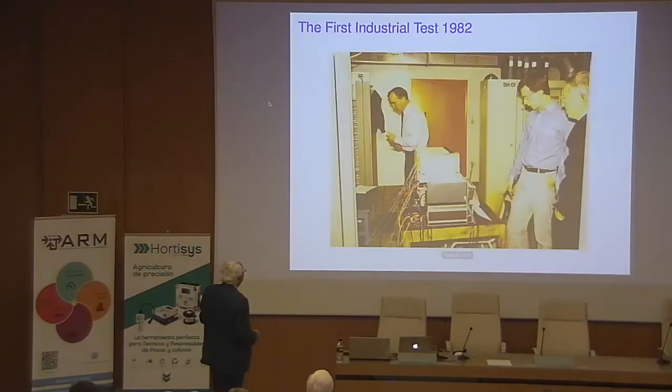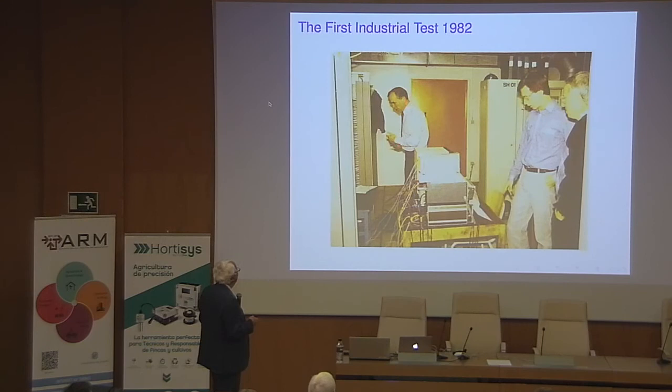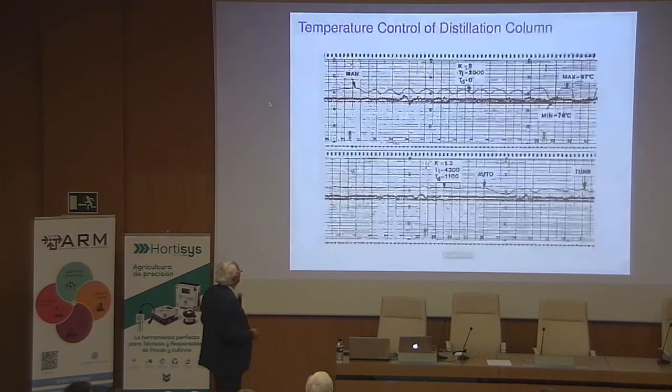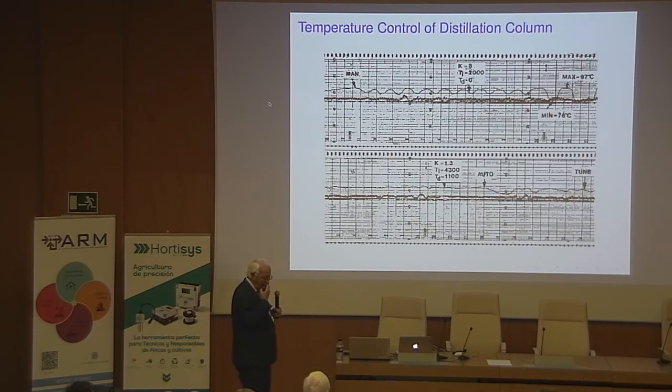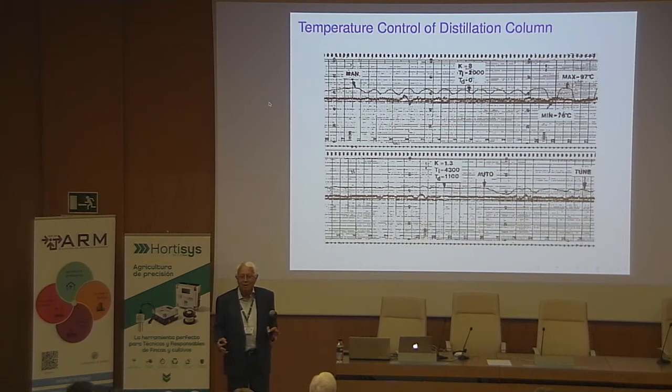Here is a young Tore, and this is the first industrial experiment we did at a sugar refinery near Lund. The computer was an Apple II with the code of the first relay auto-tuner — I actually wrote the code. When they were trying out the STM-20 system up in the north of Sweden, normally commissioning takes a couple of weeks. With the auto-tuner, they did it in two days: switch to a loop, push a button, take another one, push a button.